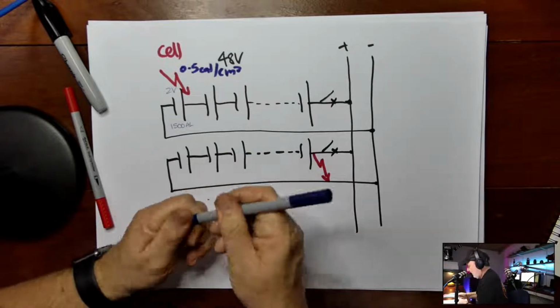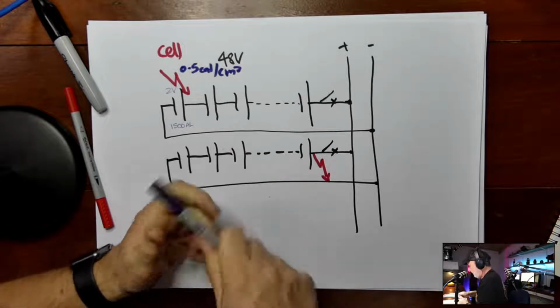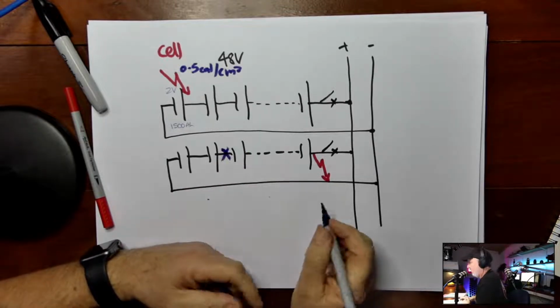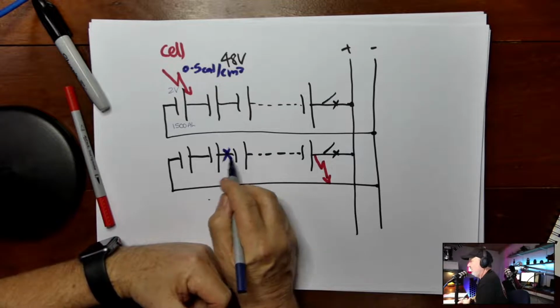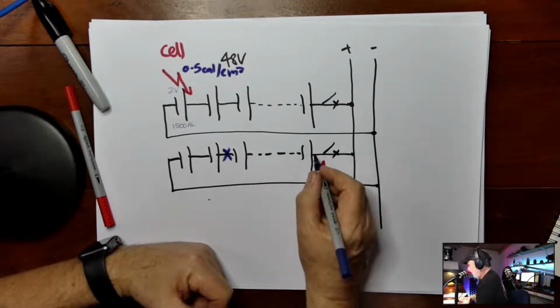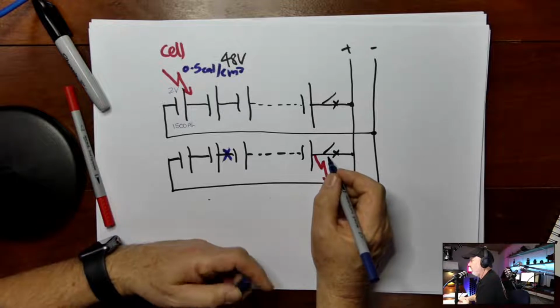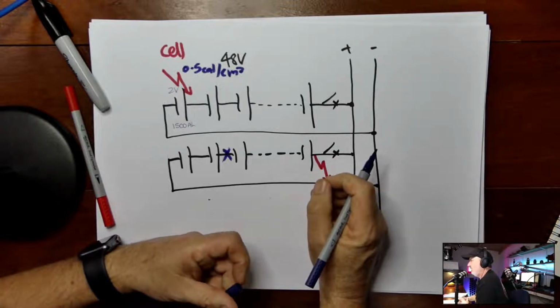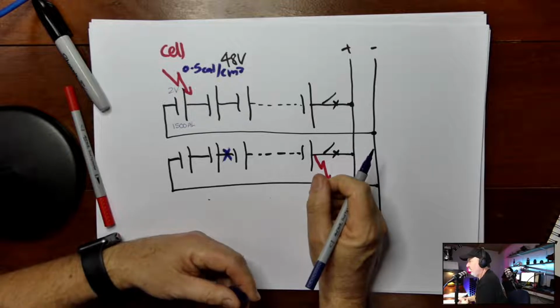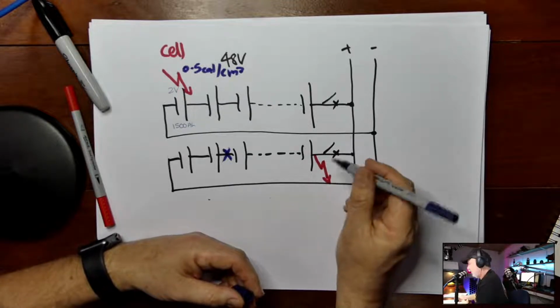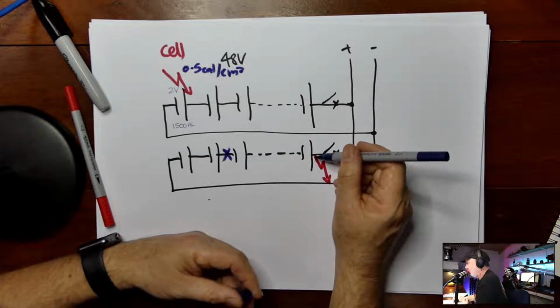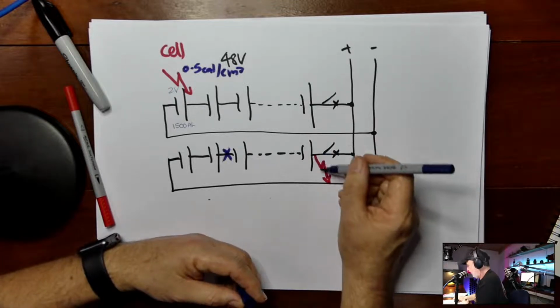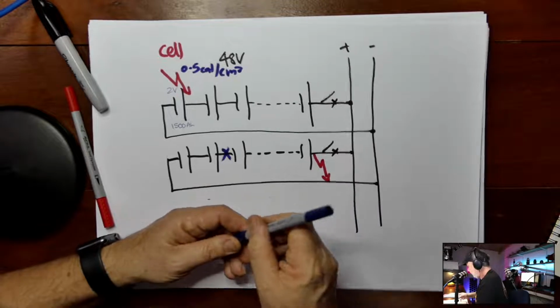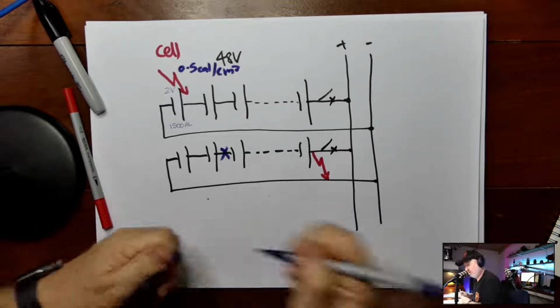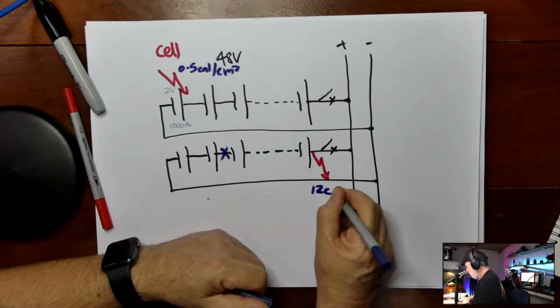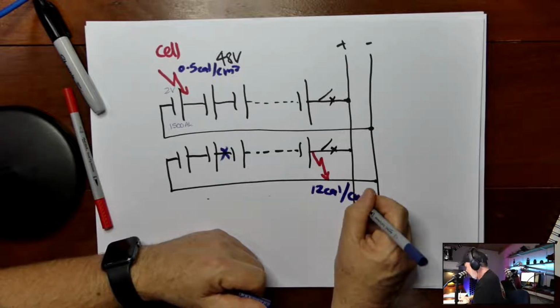So if you do not connect all of the string before you do your terminations, you haven't connected those 2 cells together yet, while you're wiring up your string overcurrent protection device. So this is where a risk assessment and a safe work method come in. How can you work safely in the system so you've mitigated or removed the risk of this fault occurring, and therefore your PPE requirements are significantly reduced? So here, if that fault was to occur, that's 12 cal per square centimetre.